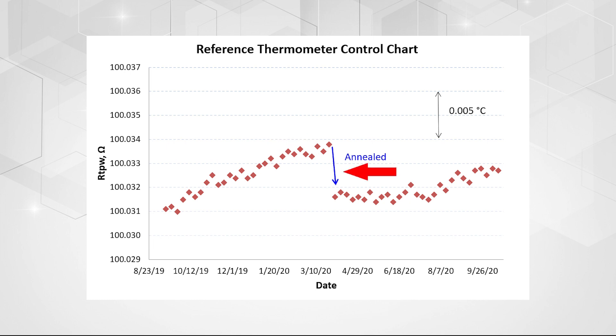The annealing process helps to relax the pent-up stresses in the platinum wire and burn off oxidation. Through this process, resistance values return to a more normal range as shown in the sample data.